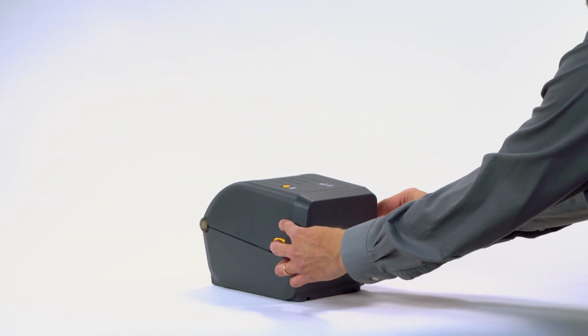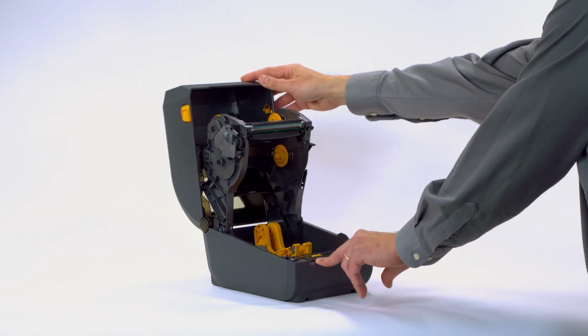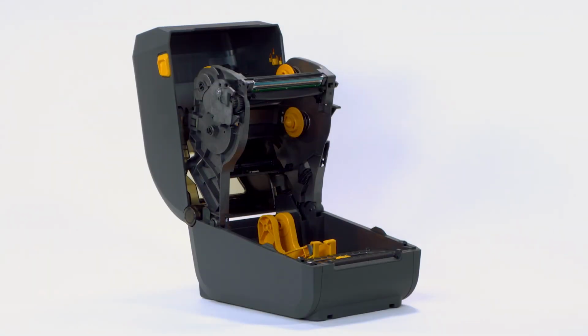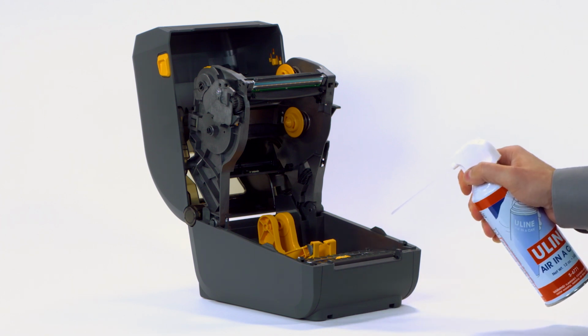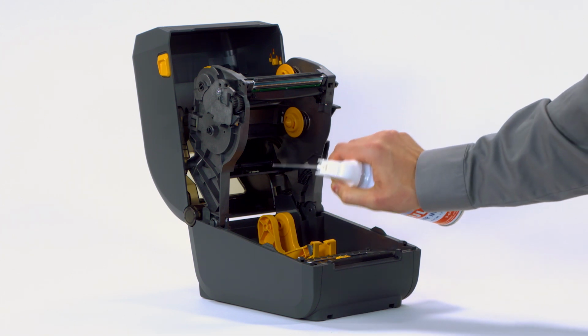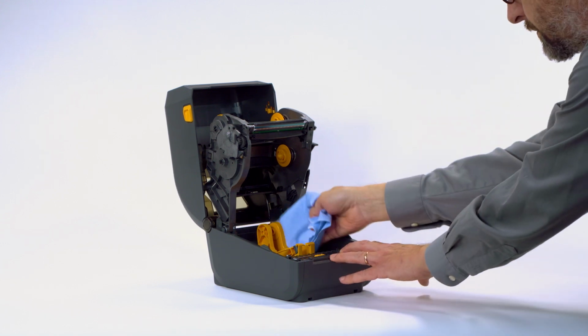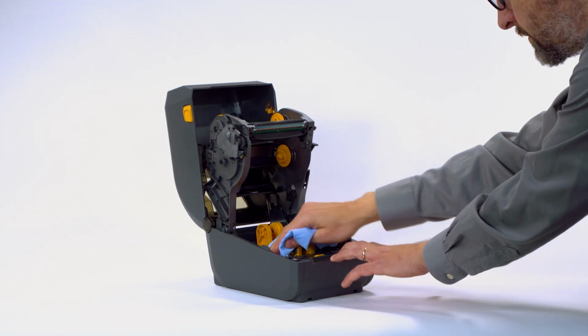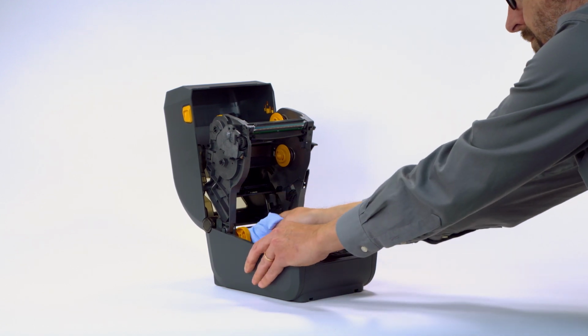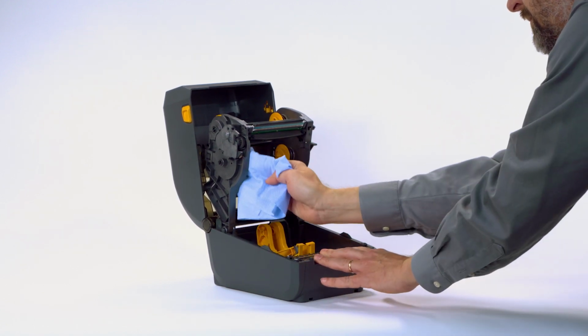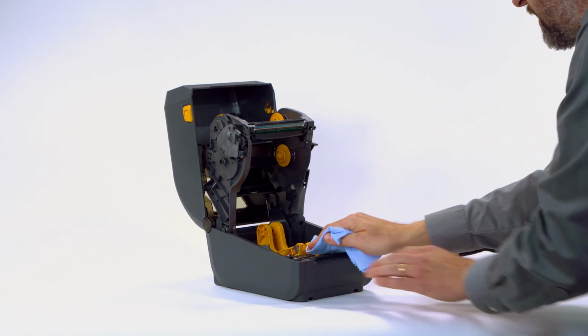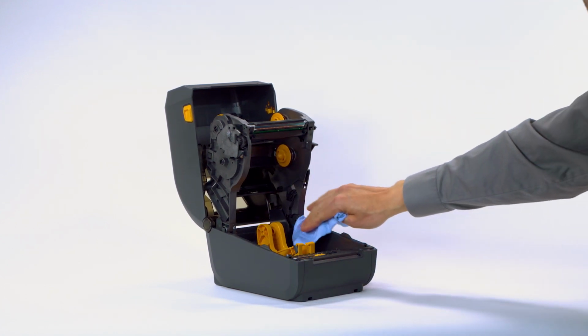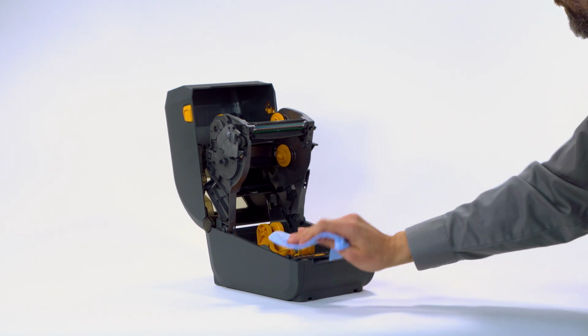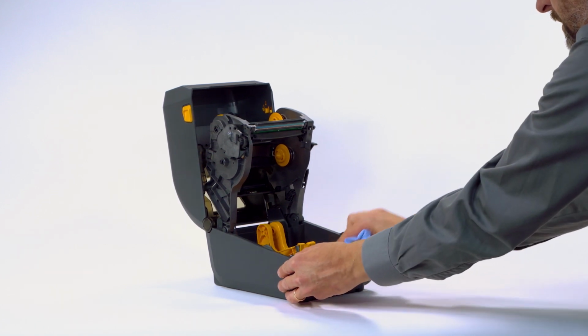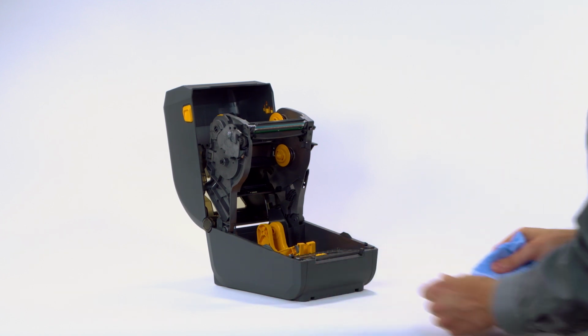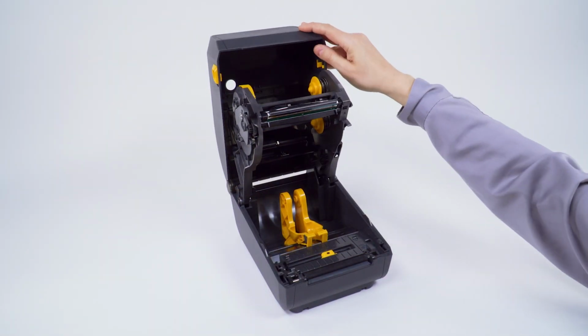Open the printer. Clean the media sensors using compressed air. Clean the roll holders and frame using a lint-free cloth or swab moistened in 99.7% isopropyl alcohol. To clean off any adhesive buildup on the media guides, roll holders, and other areas, wipe with a lint-free cloth or swab moistened in 99.7% isopropyl alcohol. Clean the ribs and sensor. Close the printer.